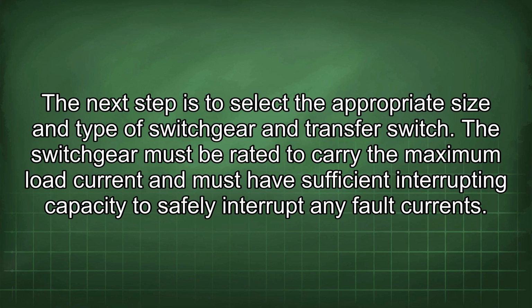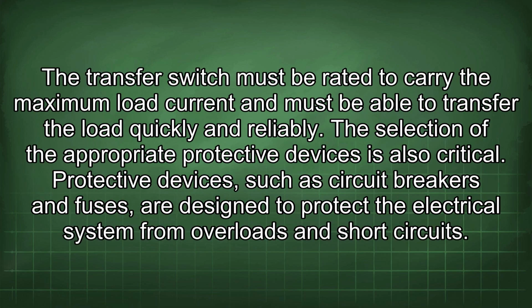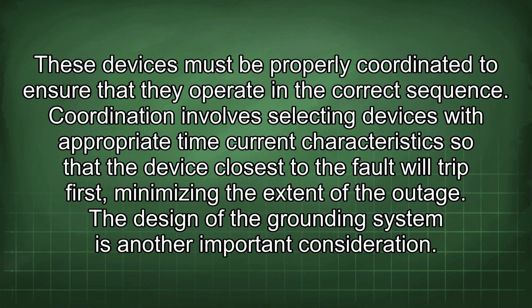The next step is to select the appropriate size and type of switchgear and transfer switch. The switchgear must be rated to carry the maximum load current and must have sufficient interrupting capacity to safely interrupt any fault currents. The transfer switch must be rated to carry the maximum load current and must be able to transfer the load quickly and reliably. The selection of the appropriate protective devices is also critical. Protective devices, such as circuit breakers and fuses, are designed to protect the electrical system from overloads and short circuits. These devices must be properly coordinated to ensure that they operate in the correct sequence. Coordination involves selecting devices with appropriate time current characteristics so that the device closest to the fault will trip first, minimizing the extent of the outage.